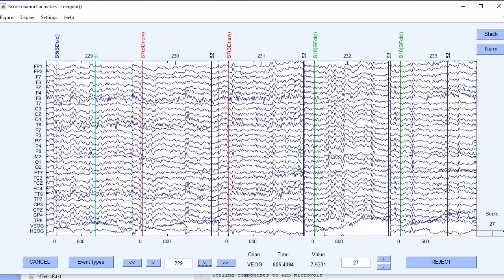The gel sort of settles and then you start to have electrode drift problems. So it's a really good practice to fill the electrodes once you've got the impedance to an acceptable level. Go ahead and fill it, otherwise you might forget to fill it.